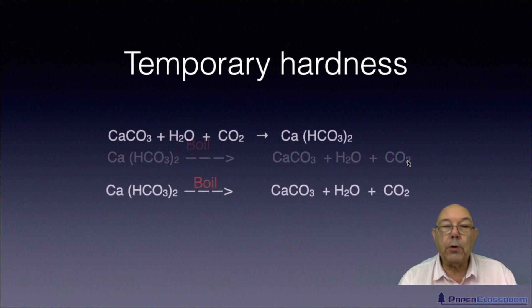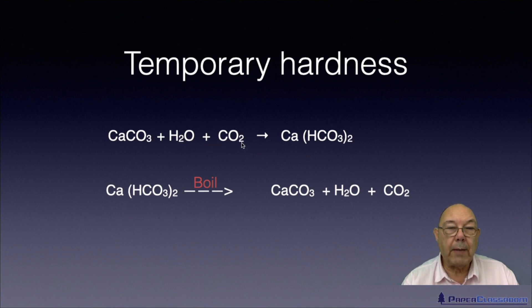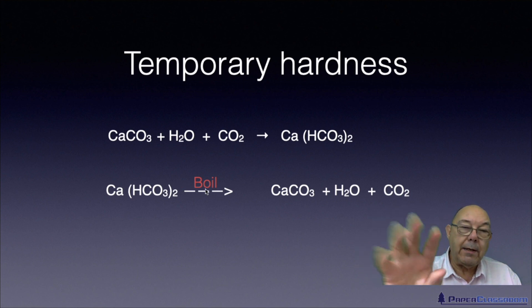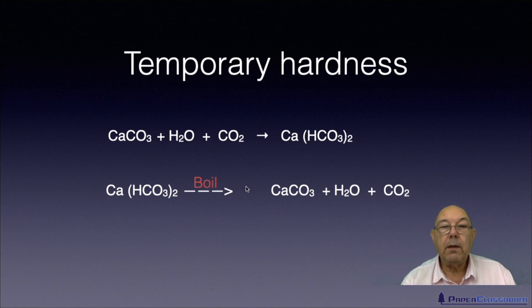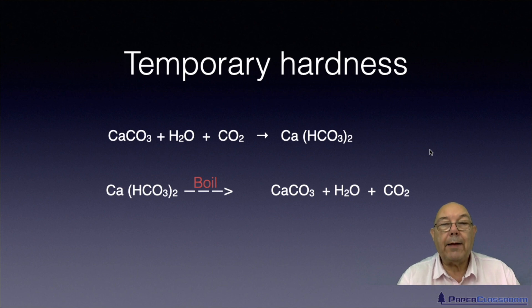We can look at those two equations together. Here is calcium carbonate combining with water and carbon dioxide — carbonic acid — to produce calcium bicarbonate. And here is the calcium bicarbonate: you need to put energy in to make it boil, and that will reverse to calcium carbonate, water, and carbon dioxide. So that's how you get rid of temporary hardness — you boil it. You then have to deal with the scale of course.